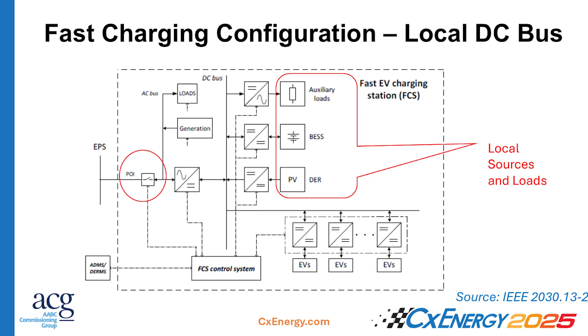I'm going to go through two one-line diagrams that give an idea of typical architectures. This one is a local DC bus charging plaza. I highlighted on the right that one common feature is there may be auxiliary loads in addition to the vehicles—in many cases a battery energy storage system, which is a DC source, often combined with photovoltaic. That provides power to the DC bus, in addition to the AC generation from the utility. The EVs are charged off that DC bus. I circled on the left the important distinction: even though it's a DC bus, the point of interconnection with the utility is the point we need to be concerned about when commissioning these systems.